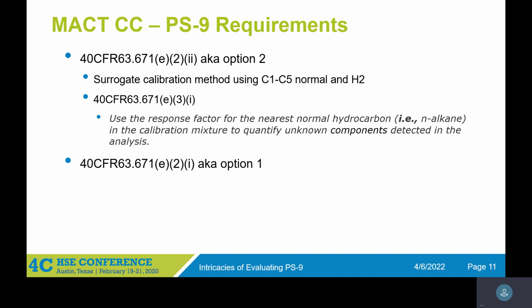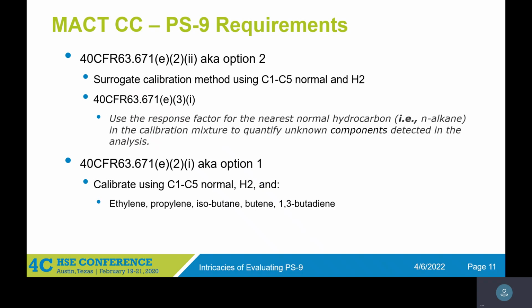So the other option is option 1. This one specifies to calibrate also using C1 through C5 normal, hydrogen, and then additional gases. We have the ethylene, propylene, isobutane, butenes, 1,3-butadiene, and then optionally acetylene, carbon monoxide, propadiene, and hydrogen sulfide. So that's a lot more gases, and those cylinders tend to be a lot more difficult and more expensive because of more gases.